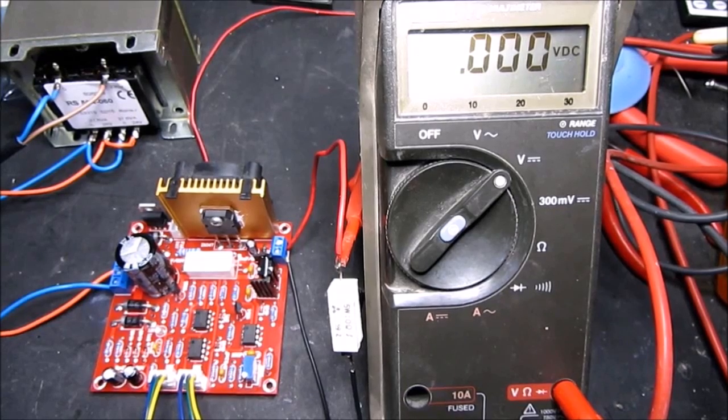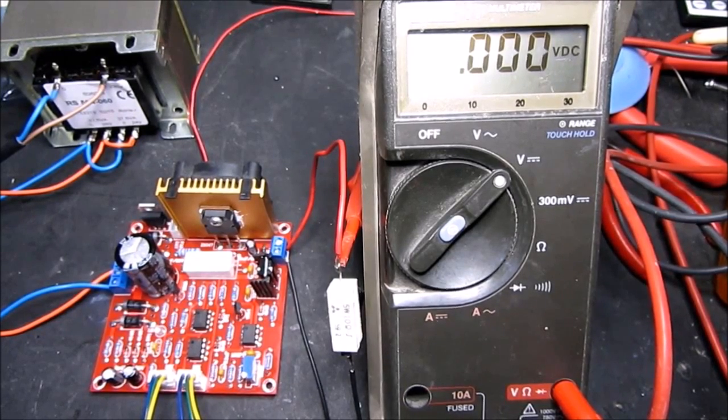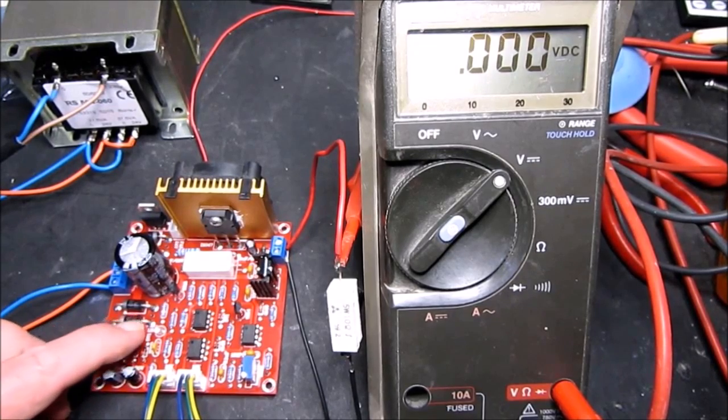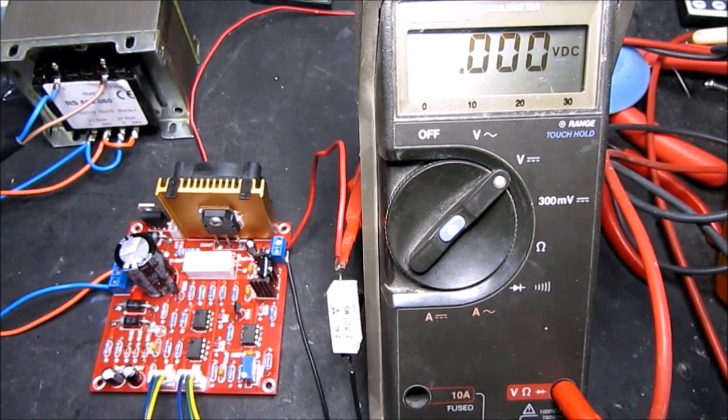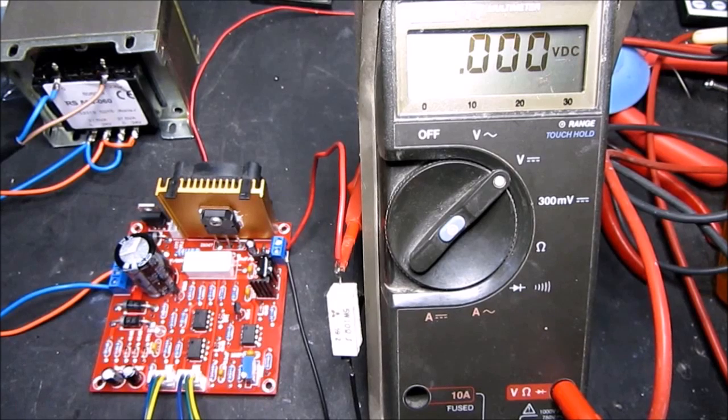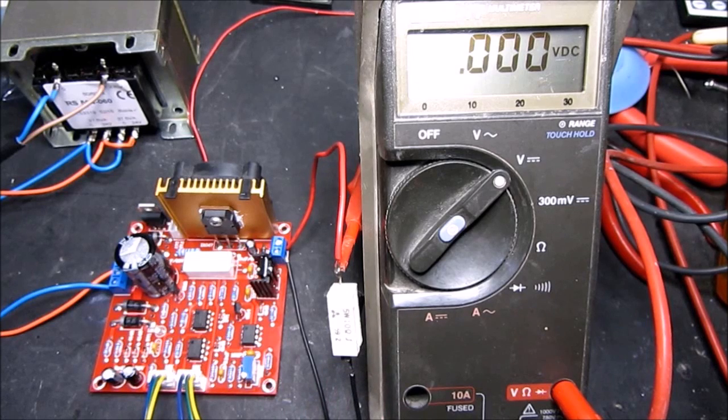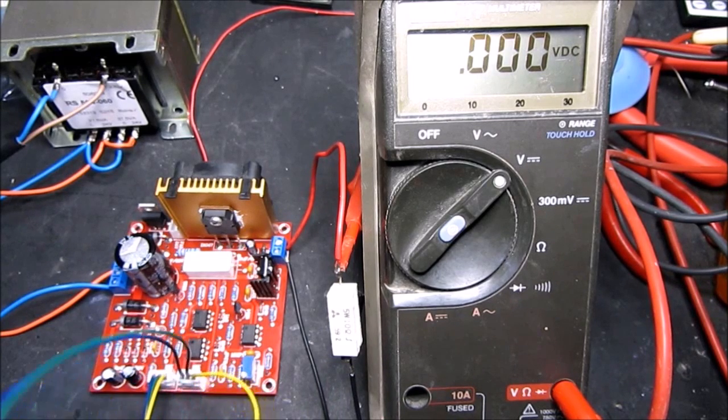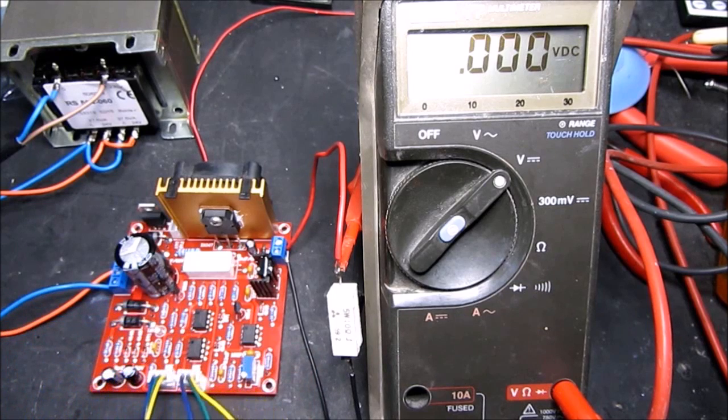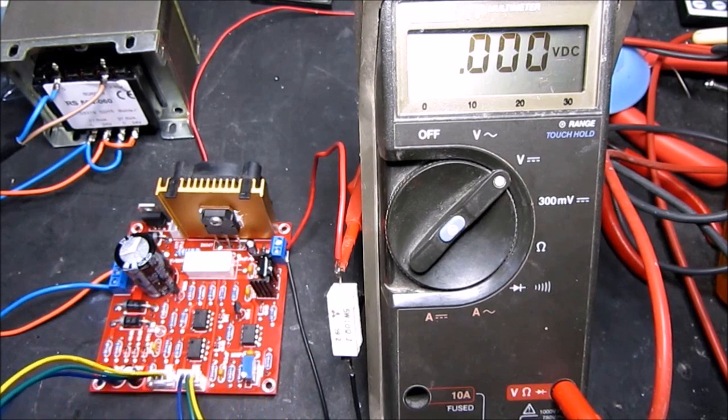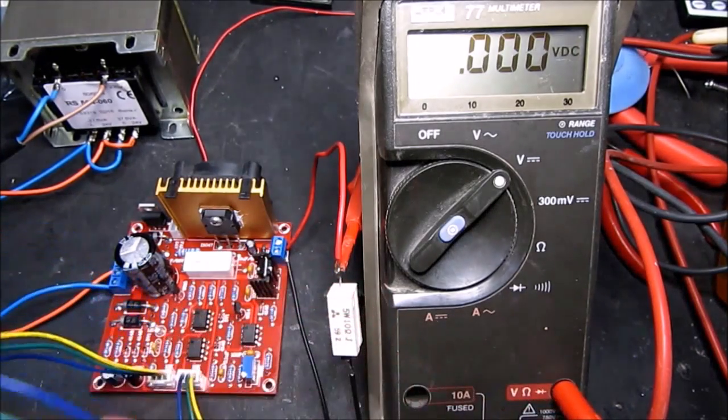The final part of the calibration is for the current limit. The current limit is indicated by the LED coming on. And to calibrate that, we need to put a 10 ohm resistor across the output, making sure that it has sufficient power capabilities. This is a 5 watt 10 ohm, because obviously we're going to be passing some current through it. And to start this test, we turn the voltage potentiometer all the way down and the current potentiometer all the way up. So that's fully clockwise.